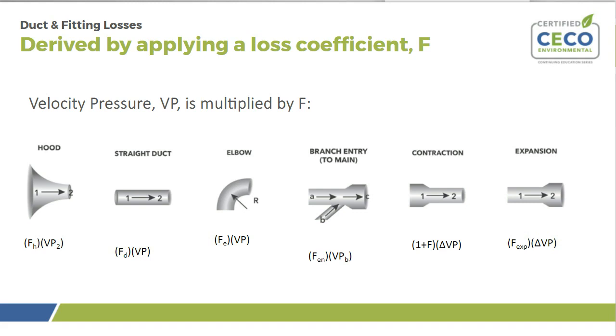Vern had that slide showing the different shapes of the hood. This is a bell mouth. It's the lowest loss hood you can have. For straight duct, the loss is caused by the friction factor on the internal wall of the duct. So the larger the diameter of the duct, the lower the loss you're going to encounter for that duct. But it's also dependent on velocity and system volume.